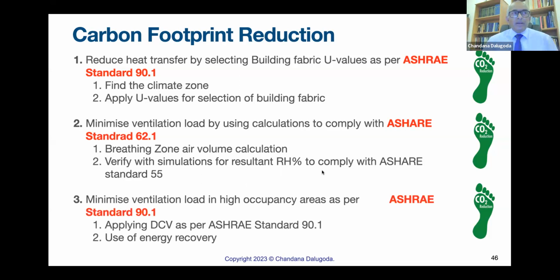Next, the areas of the building sometimes you find densely populated. If you take an office building, obviously we have meeting rooms, auditoriums, these are called densely populated. How does ASHRAE categorize this? 25 people per 100 square meters and above. 25 people per 100 square meters and above are called densely populated areas. Now in those areas, we'll have to adopt the demand control ventilation method to drop energy consumption. Not even that, sometimes we'll have to use energy recovery.